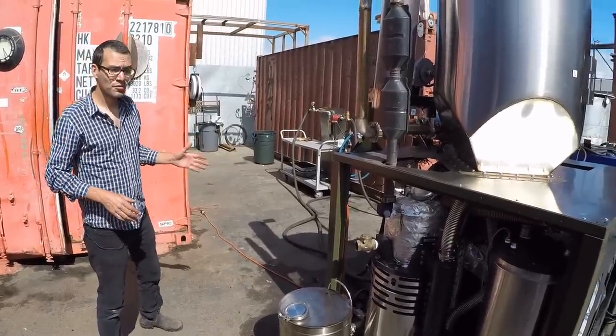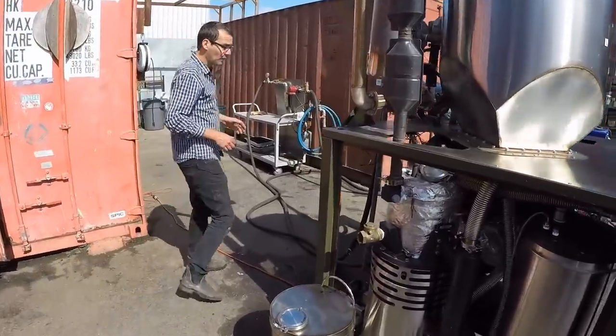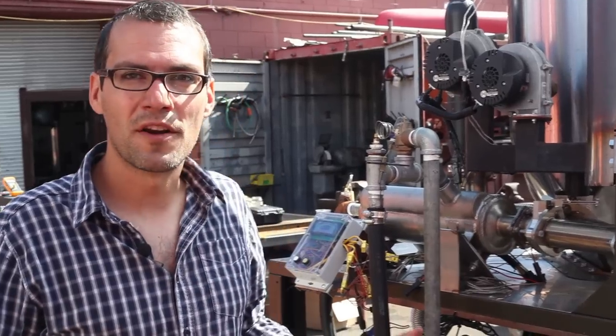The combined heat and power system, or CHP for short, mounts on the back of our power cube. The CHP system takes water in at 60 degrees Celsius and delivers it out at 80 degrees Celsius, and it heats that water up 20 degrees in two stages.